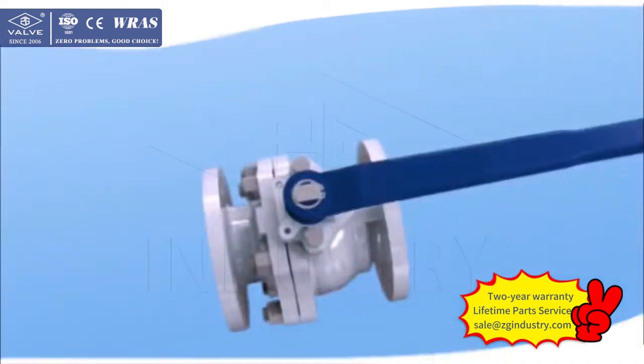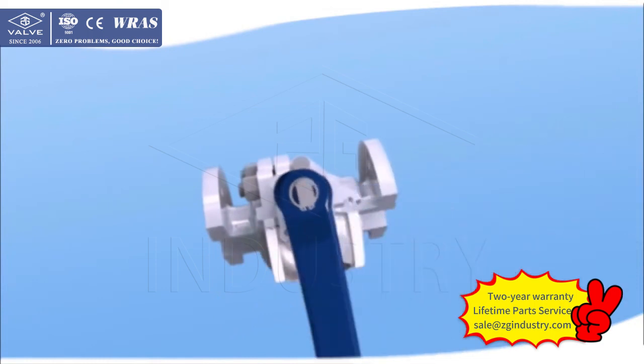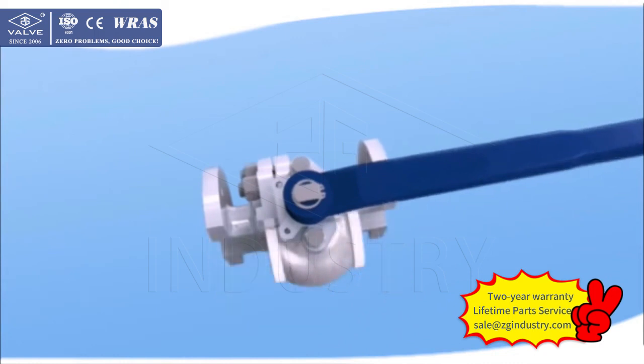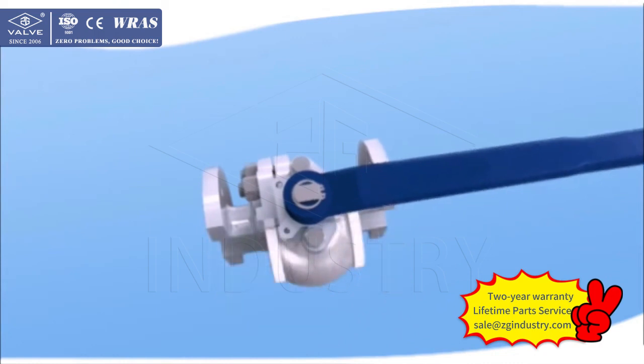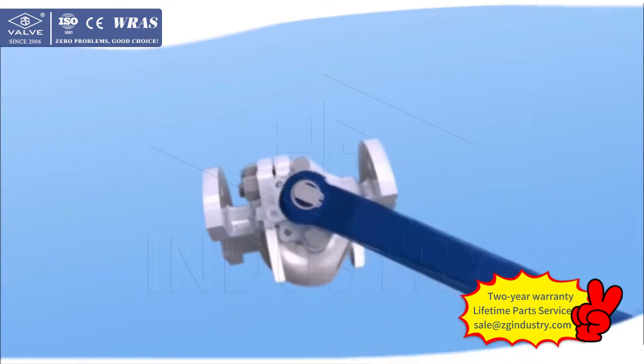The structure characteristics of floating ball valves made by VARC are as follows. 1. Switch indication of the valve. The head of the stem is shaped flat, so it is easy to distinguish whether the valve is in the on or off position. When the handle or stem flat is parallel with the pipe axis, the valve is at the on position. When the handle or stem flat is perpendicular to the pipe axis, the valve is at the off position.